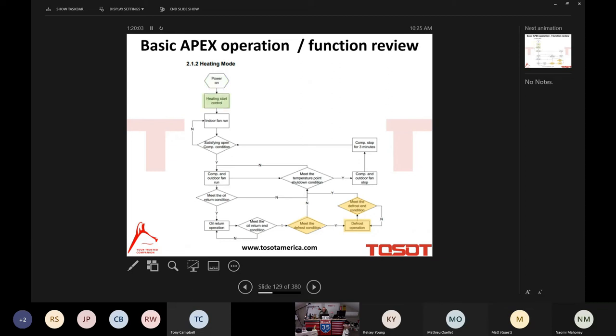Again, we power on. We have an active call for heat. Indoor fan operates. Compressor and the outdoor fan begin to run. Again, if there is a need for the oil return feature, that will take place. Then we meet our set point temperature setting. The compressor and the outdoor fan are de-energized. And once again, there is our 3 minutes off and 3 minutes again delayed to start for a minimum of 6 minutes off.